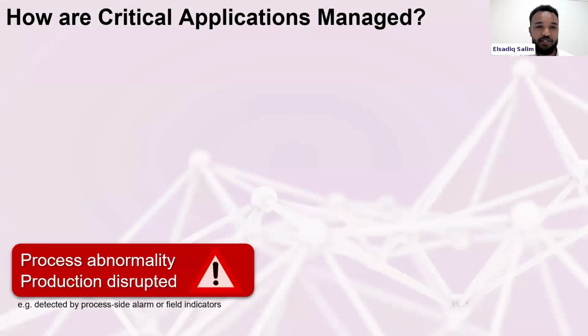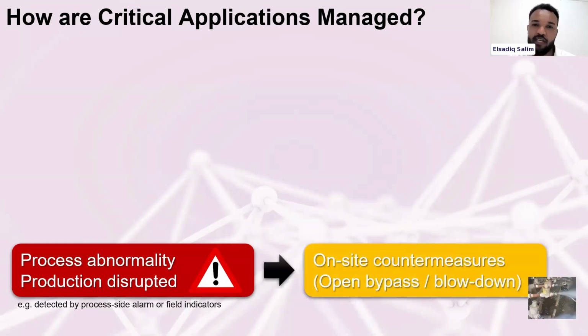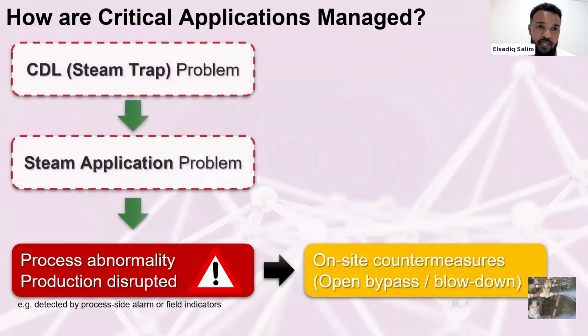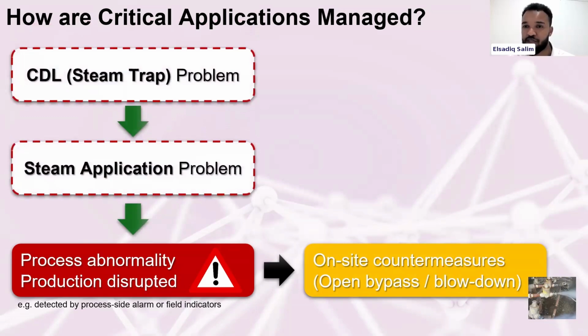Those critical locations, more painful can be if we get a process abnormality. So if you've got a jacketed kettle or some cooker, you won't notice a failed steam trap, but you'll notice the uneven heating on your batch process, and you might need to dump that batch. So on site, we take countermeasures. We open a bypass valve, or we blow down the system to make sure that the heating efficiency can still go on. This is an example of a steam trap issue affecting your process massively.